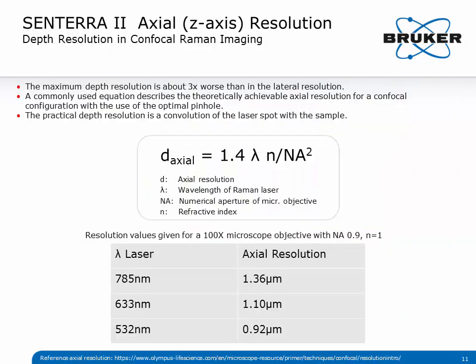We also want to talk about depth or axial resolution. It is very commonly defined as 1.4 times the incident wavelength times the refractive index divided by the square of the numerical aperture. In the table below, you can see the best possible resolution for each wavelength.